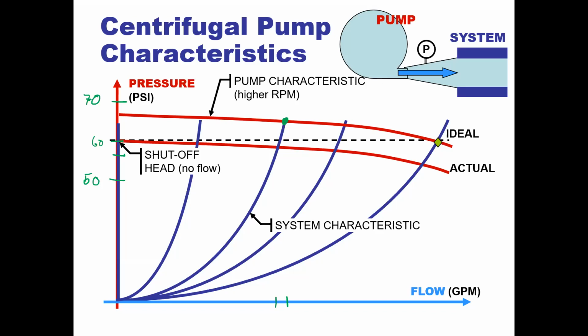So now, if the RPM increases, does the ideal also increase as well? It would increase to wherever it's running at. It would have its own ideal line, but honestly, you don't really pay attention to ideal lines. That's just stating that if you're going to call it a 60 PSI pump or what have you, that's where it's going to be. Just because you're sitting at this position doesn't mean that you're not going to call this pump a 60 PSI pump. That's still going to be its designation because that's what it should be running.